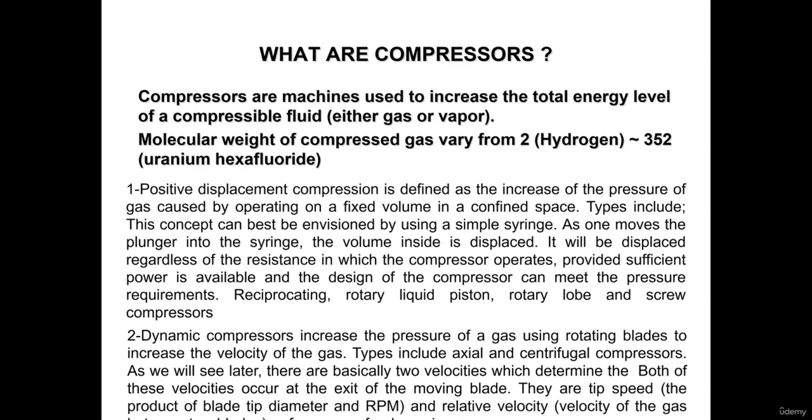But in compressors, the gas density changes, that's why it's compressible. This compressible effect will affect the performance of the compressor. If any parameter changes the density, then the hydraulic performance and output of the compressor will change.